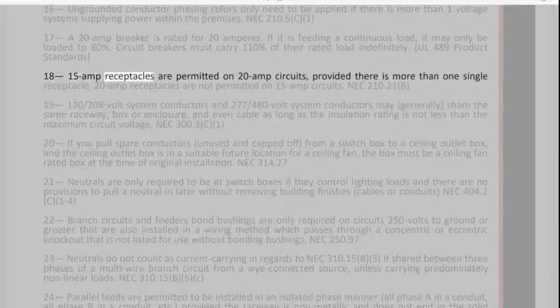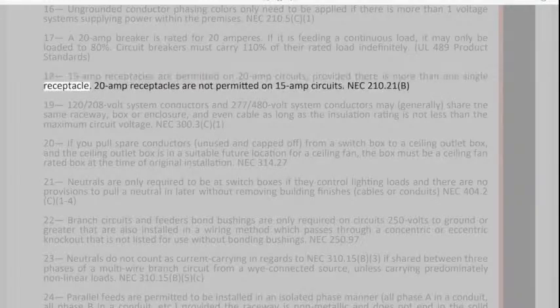18. 15 amp receptacles are permitted on 20 amp circuits, provided there is more than one single receptacle. 20 amp receptacles are not permitted on 15 amp circuits. NEC 210.21b.